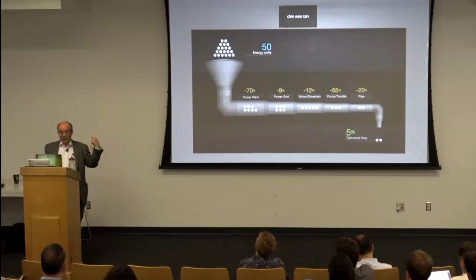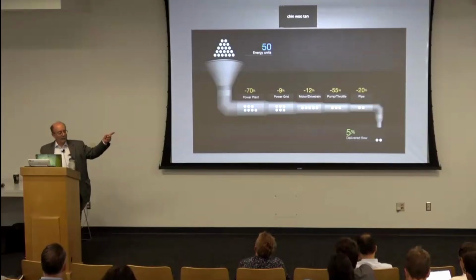As you go back upstream, the components get smaller and cheaper, reducing the total capital cost. So always start your savings downstream. Start at the end, with intent, with purpose. Do you even need the flow? Passive buildings and equipment will need less or no pumping.